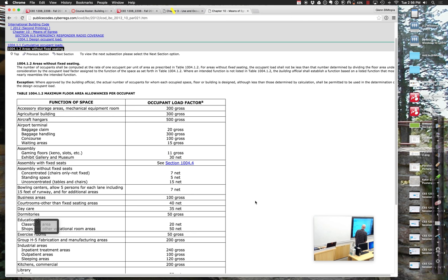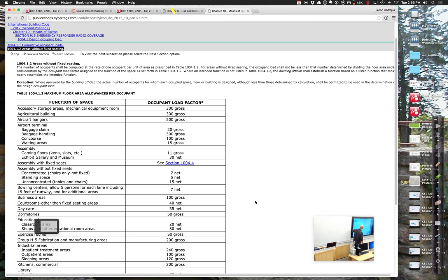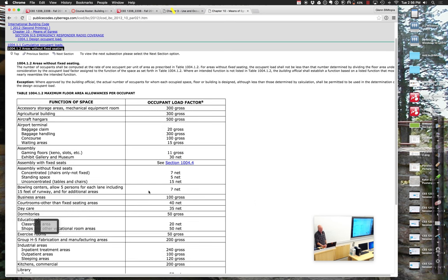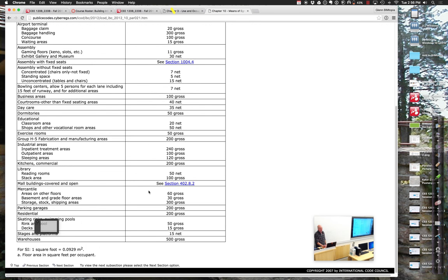So for each of your different spaces, as you do your space planning spreadsheet, think about what the load factor is relevant to that space — that tells you how many people you have to consider as being there, really what your design factor is. For residential, it's about 200 square feet per person, so a 1,000 square foot apartment might assume 5 people.